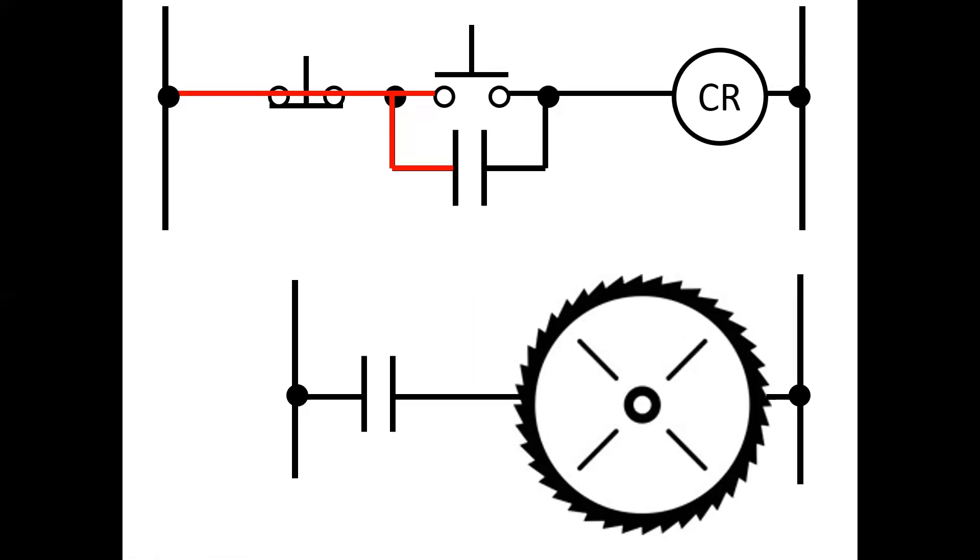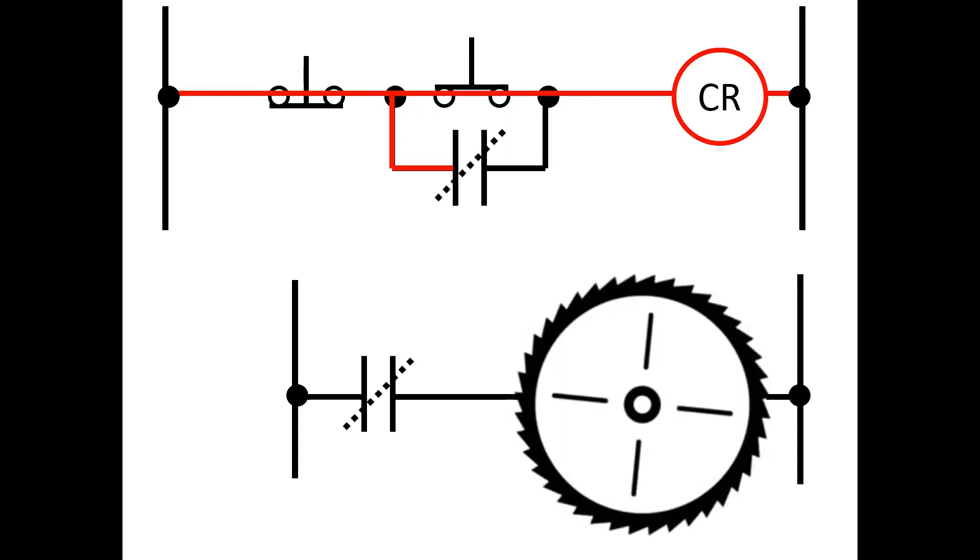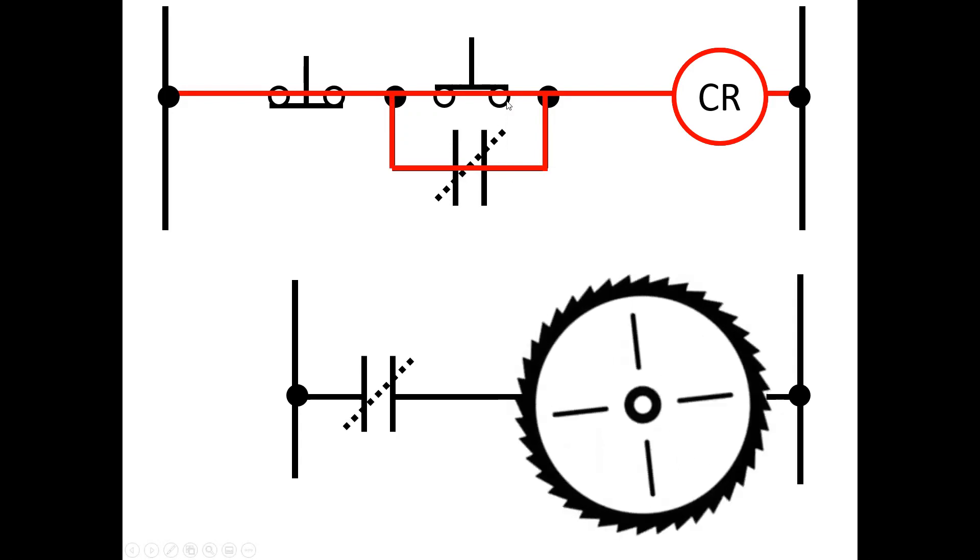So let's see what happens. The first thing is we close the push button for start and it energizes the coil, at which time the coil changes the state of all contacts. Notice what now happens. We have a parallel path for current to flow. It is now flowing both through the closed contact and through the push button.